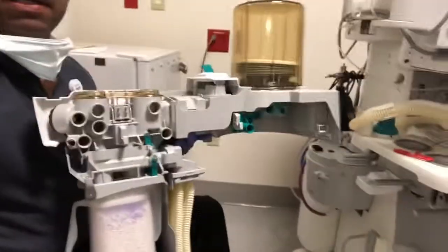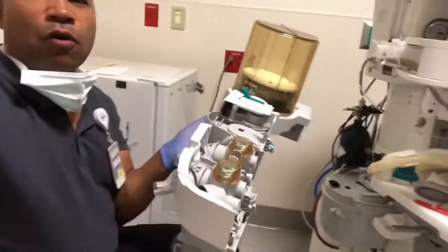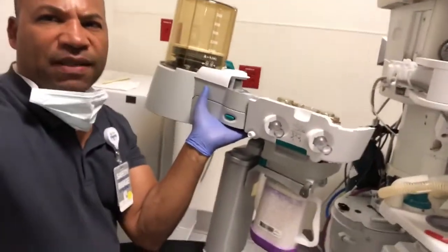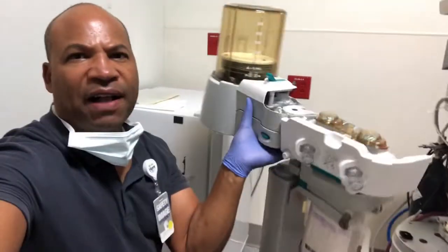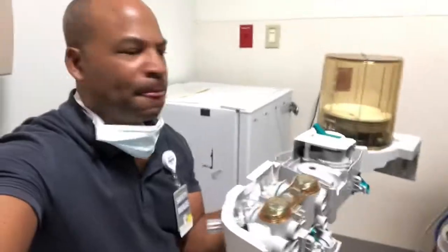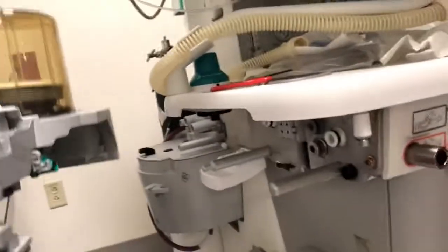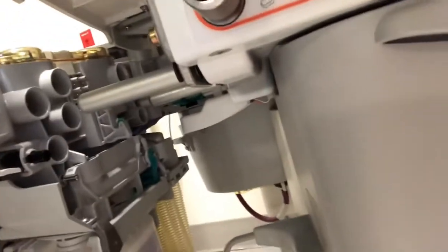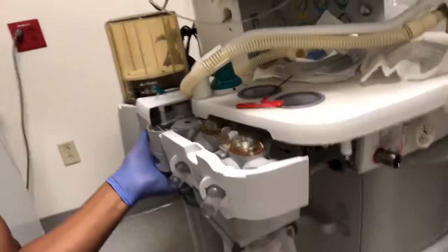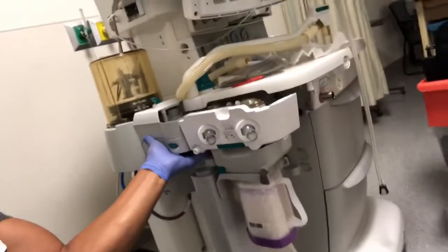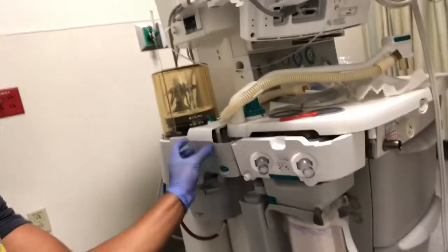All right, so let me show you now as I put this back together. This is what the assembly looks like once it's all put back together. This is here for our pneumatic system, and this is where your APL valve and all your flow sensors and valves go into. And here on the side of the unit, if you can see it, this really lines up. And you basically just slide it back into the actual chamber. And once you line all this up, let me just lift it up a little bit here. You can see the side of the unit here. And once you have everything in place, this all pushes right in.